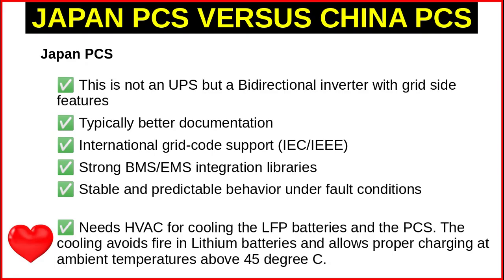This Japanese PCS is not an online UPS but a bidirectional inverter with grid side features. It has typically better documentation. It has international grid code support. It complies with standard committees like IEC and IEEE. It has strong BMS, EMS integration libraries.